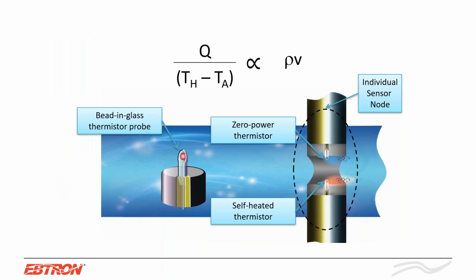So let's look at thermal, because I think this is really important. And this is really what sets EBTRON apart from other airflow manufacturers. Basically what we have here is our sensor node, and we have two thermistors. These are medical grade thermistors. They were actually designed for NASA during the 1960s, the Apollo space program, because they can survive extreme differentials in temperature. We have one thermistor that's self-heated, and we have one that's zero powered, right? And we have multiple of these in our probe, right? So we call this complete package a sensor node.